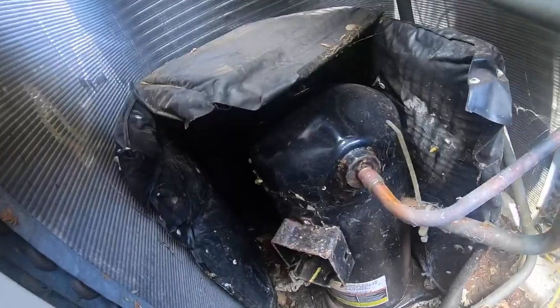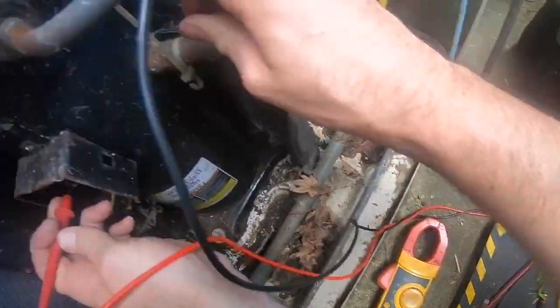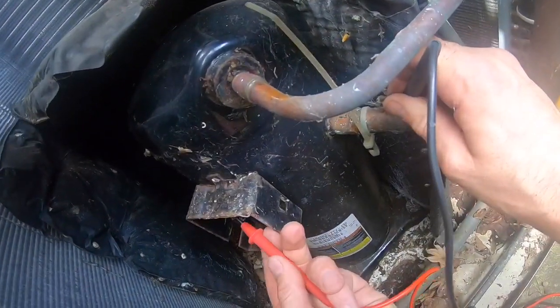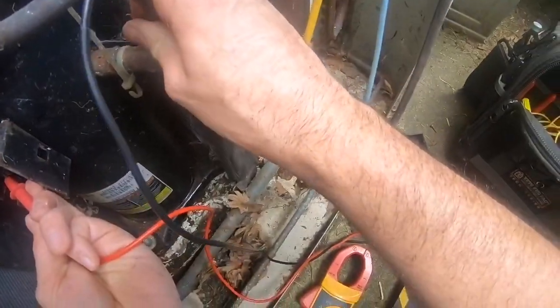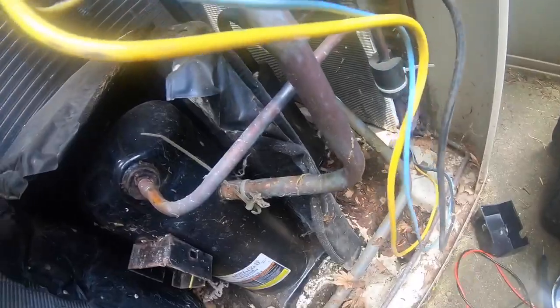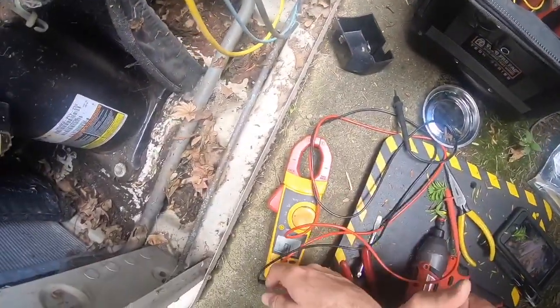But you have a grounded compressor itself. Compressor is grounded. The service call ends here because unfortunately we have a grounded compressor. Until next time — thanks for watching.